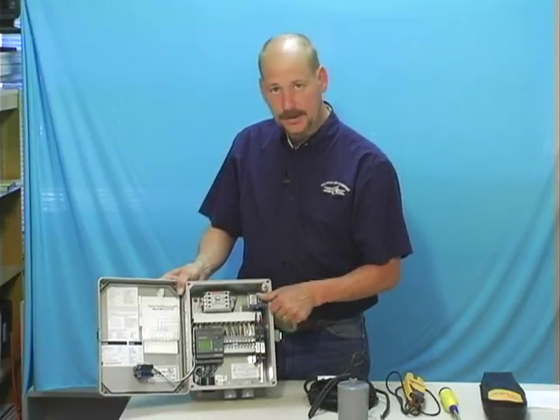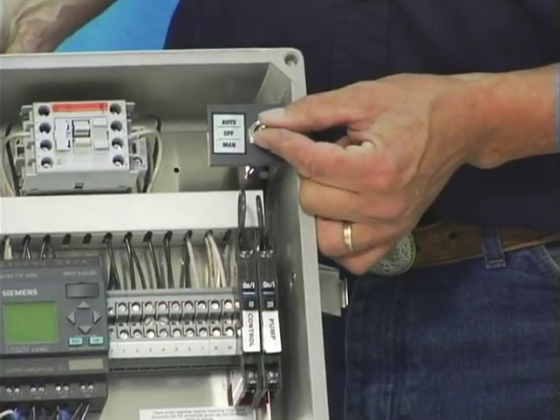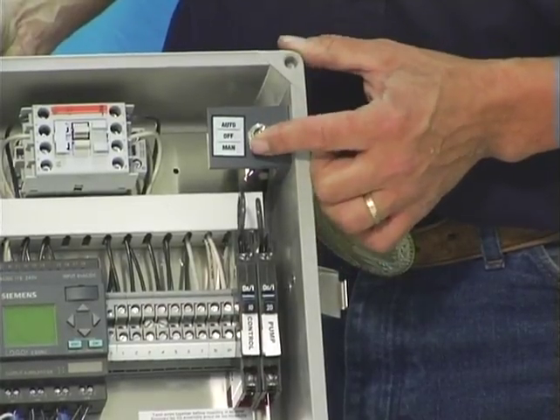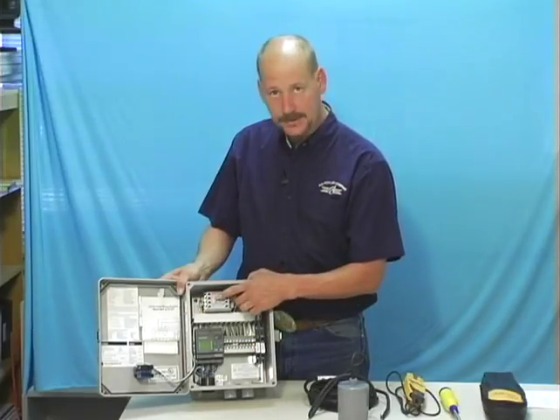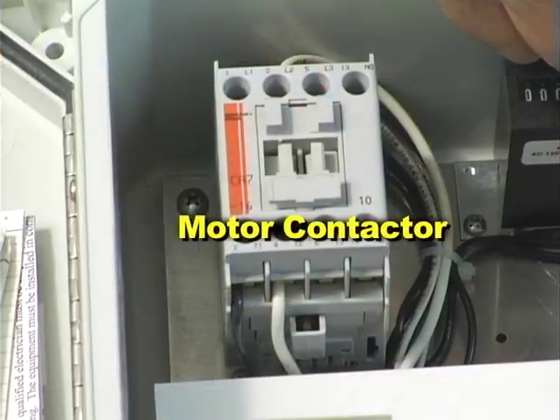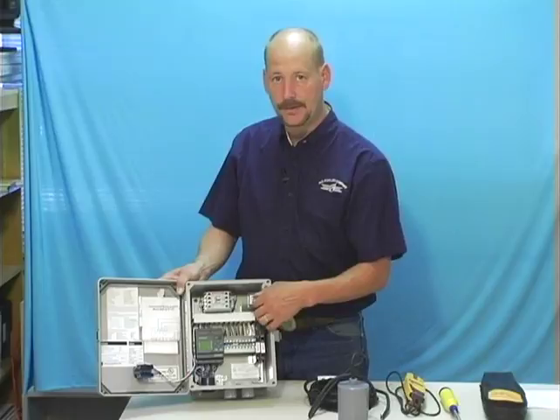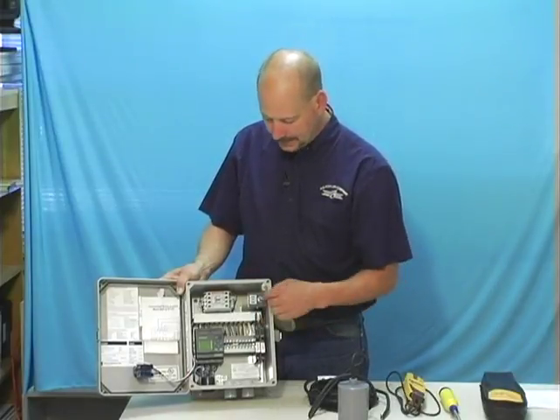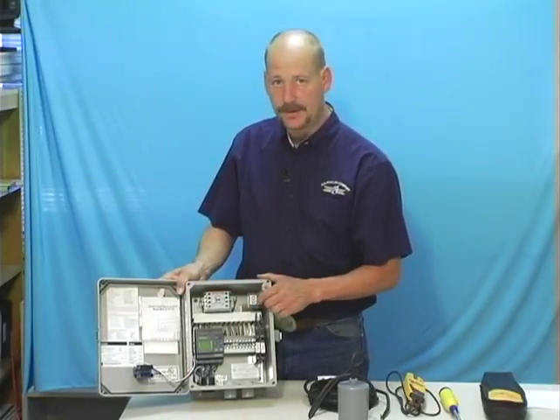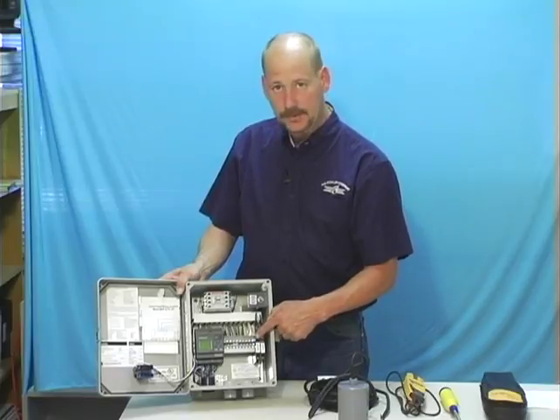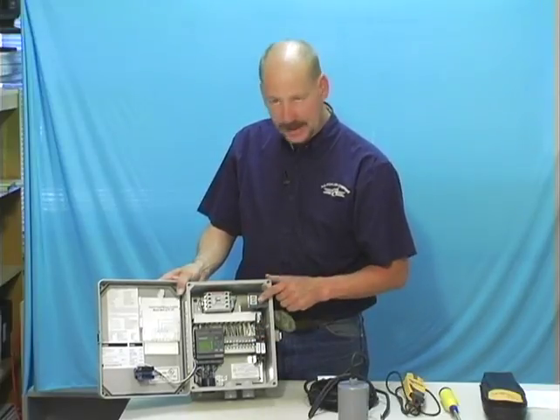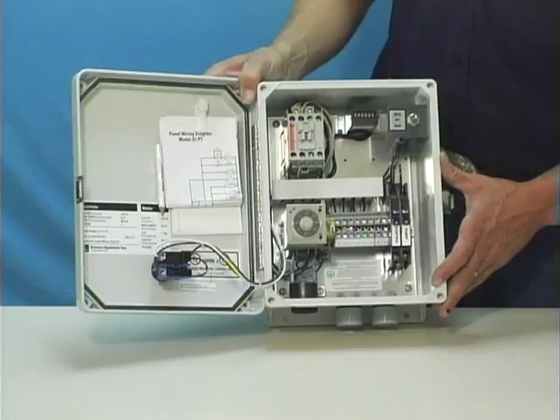Another thing you can do is take the hand-off manual switch and flip it into manual, and ensure that the motor contactor engages. If the motor contactor engages, that lets you know that you do have control power throughout the control panel. This will be the same with virtually all of the control panels. You'll have a control power in, and you'll have a hand-off auto switch.